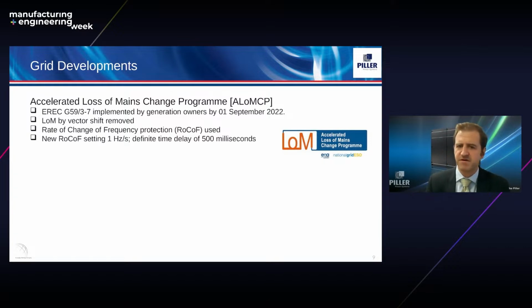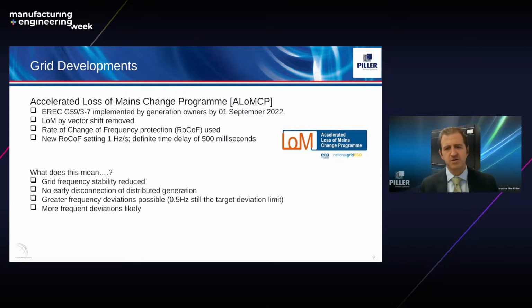This actually changes the detection method for loss of mains, therefore no longer allowing vector shift, and they're also requiring an increase in the rate at which the frequency can change, but not the actual ultimate frequency limits that are applied. But what does this actually mean? Well, the grid is no longer as stable as it once was. It's not locked to that fixed 50 Hz frequency as it used to be. So the stability cannot be maintained, but they're trying to avoid the early disconnection of distributed generation sources, which causes an event to rapidly worsen when perhaps the system might in fact be recoverable in other circumstances. This is an unavoidable result, though, of the use of embedded VRE that use inverters to generate a sinusoidal waveform rather than the synchronous machines used originally.